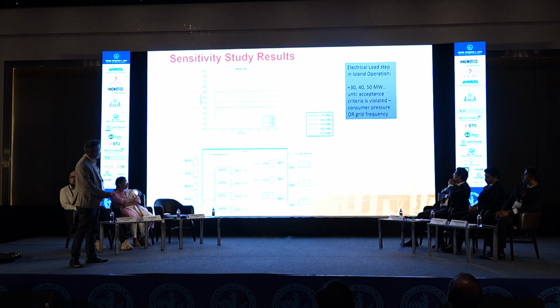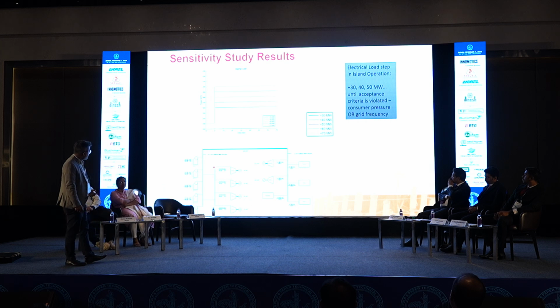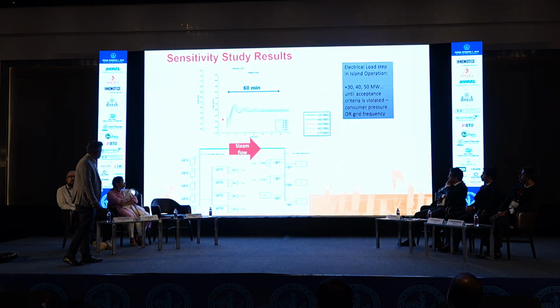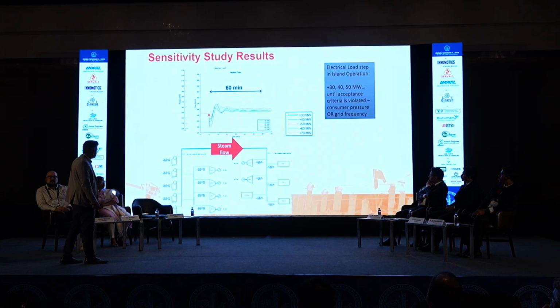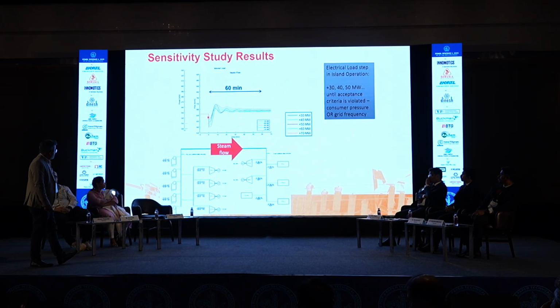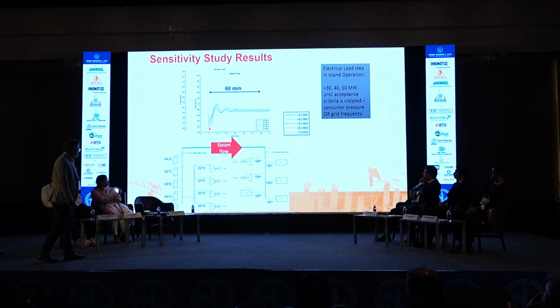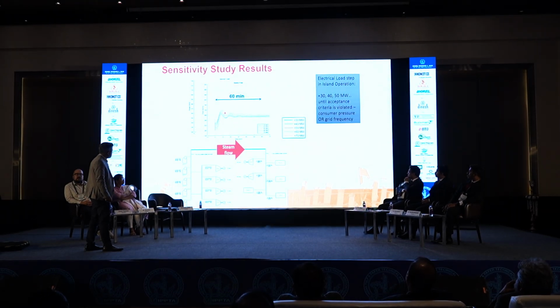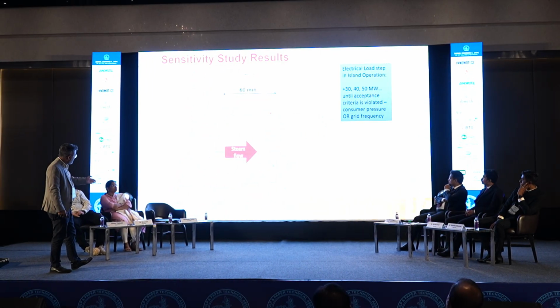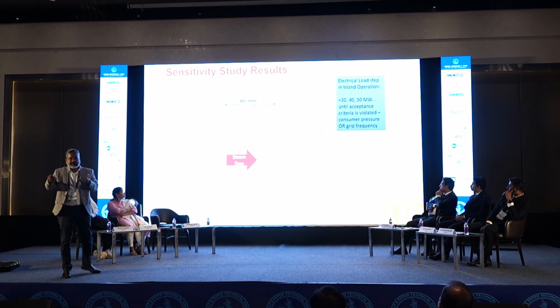So in this case, we started with a load step of 30 megawatt. We gradually increased it up to 70 megawatt, and we have seen how the steam flow will change. So the steam header flows, if you see here, the purple trend, which is of 70 megawatt, is something worth seeing because it is the largest load step, and obviously initially it will have a dip and then it stabilizes because the boiler takes time to ramp up to deliver that amount of steam.